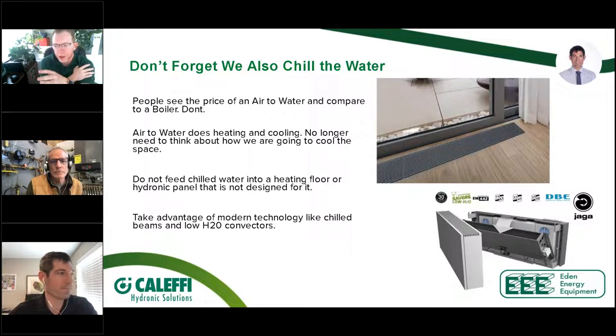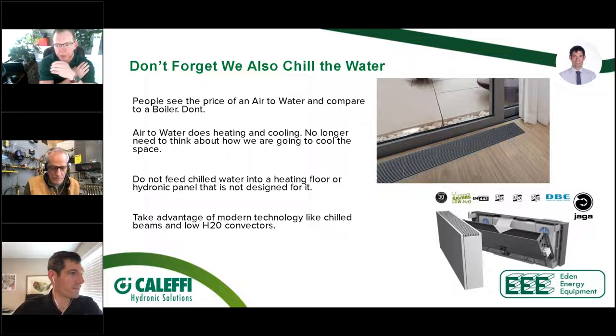So these products are more money than a traditional panel rad by a factor of about 50%. But again, you've driven the COP of the system so high that for the life of that system, it's going to be very, very cost effective. The other thing is, if this was a job, like say we put this into Bob's house and you look at that top picture, let's say the floor is all radiant. Well, how are we cooling that now?